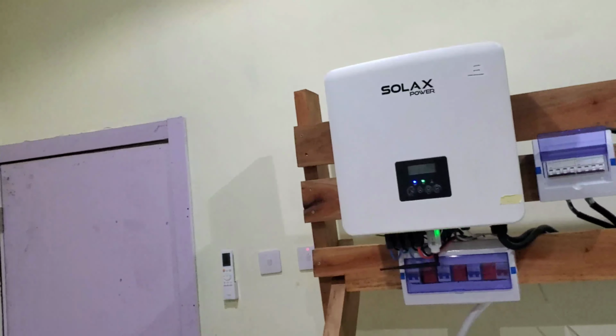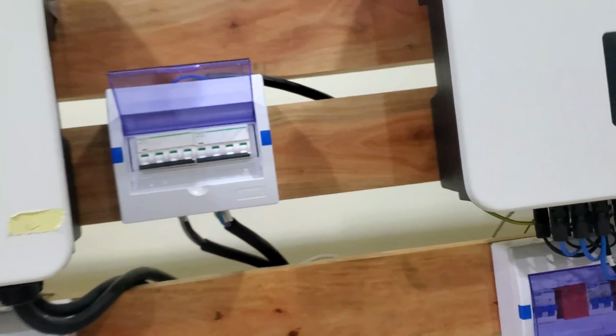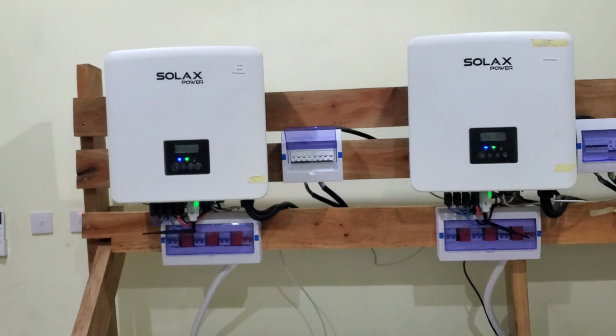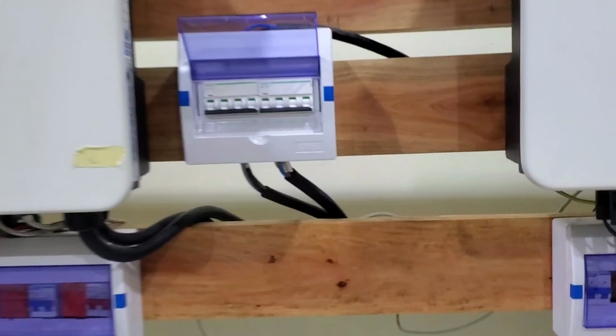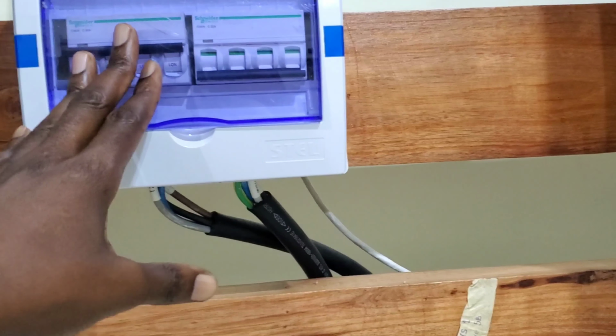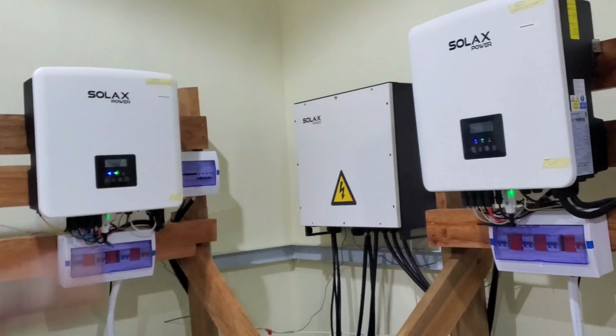Someone had asked me a question: if one inverter is not outputting power, does everything come down? This was in response to experiences we had at the other mini grid, or micro grid, we had done. The answer is actually no, because I went today, and this room and this building is powered by a system, and I'll show you how it's connected later. I started turning these breakers off, and when I turned this one off, the power went off. When I turned it back on again, the master communicated with the EPS parallel box, and then power came back on again.